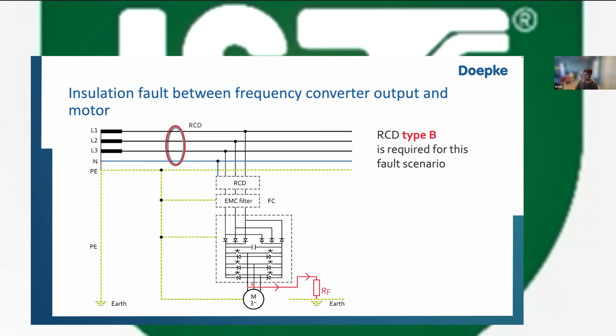If you get a fault current that is happening after the VFD, between the VFD and the motor, for example, then you get whatever frequency the VFD is outputting, which is usually not 50 hertz, right? That's how you control the speed of it. So this is what you get. And once again, type B.